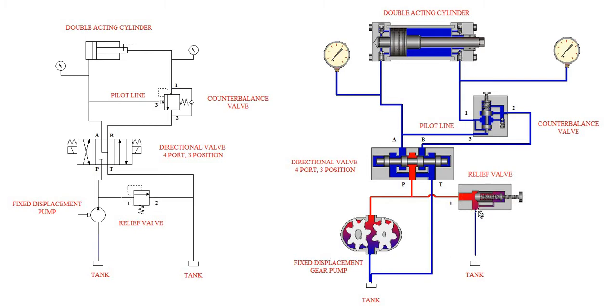And it's the same thing here. 1 is the inlet in this animated depiction, 2 is the outlet, and if the pressure at 1 is such that it exceeds the spring setting of the relief valve, it'll actually move the poppet off its land and open up a flow path from 1 to 2.